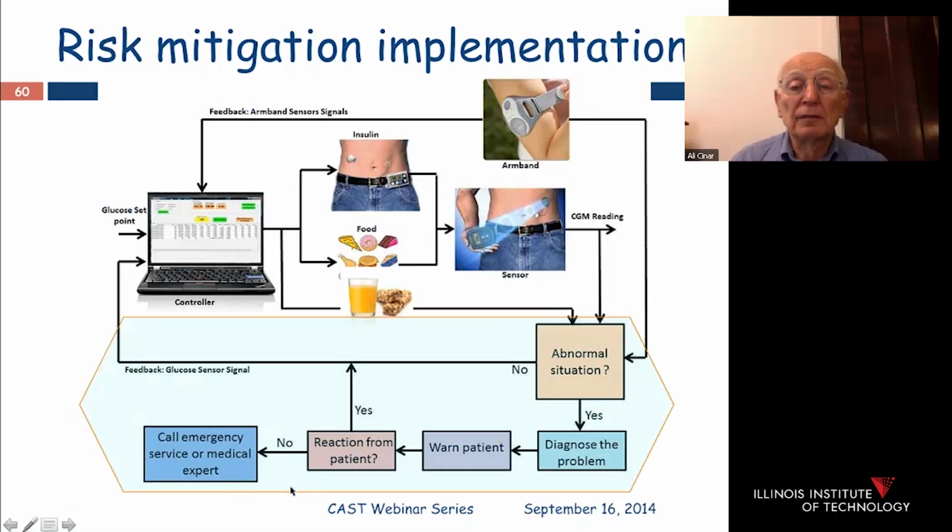And this can fit in with what we have as another module that will collect this information, do additional work, and provide some feedback to the system for doing activities such as use of estimates as opposed to actual values, filtering of data, retuning of the control system over time.